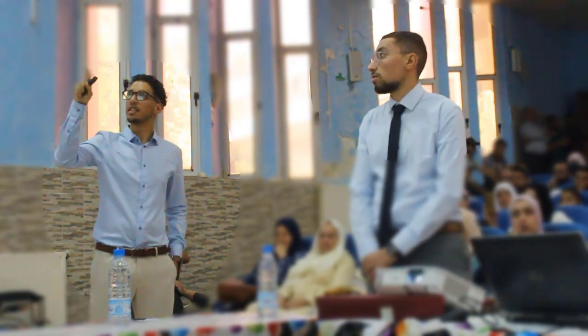Now in reality, we will have a gamma ray source having a number of photons, and having a number of photons means having a number of pulses, and therefore having a number of maxima values. This number of maxima values will be classified by a multi-channel analyzer using a RAM, where each detected maximum value will be stored in the RAM. Each address in the RAM will represent the channel value, and it will store the number of counts.